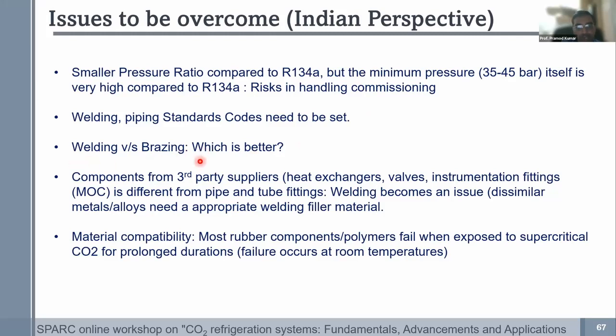Then there is always a question, which one is better, welding or brazing? It depends on who performs it, actually. If you go with brazing, it is certainly silver brazing. Then what is really puzzling is that even for the compressor, the oil separators and oil level switches are supplied by third parties. Why are the compressor manufacturers not providing these as optional or standard systems on their compressors? The oil management is again a third party device.